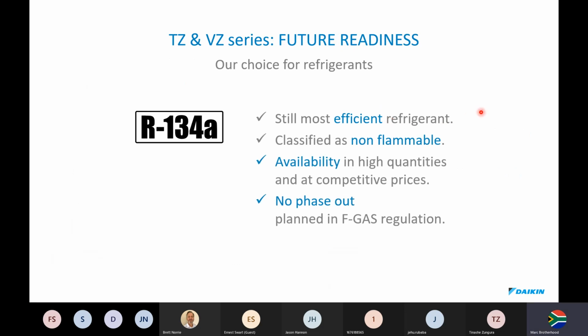So the Daikin choice of refrigerants for water-cooled is 134A. It's still the most efficient refrigerant for thermodynamic properties. It's classified as non-flammable, available in high quantities, and the good thing is there's no phase-out planned. So even in the Kigali ratification that South Africa signed, we're not phasing out 134A refrigerants. It's here to stay for quite a while.